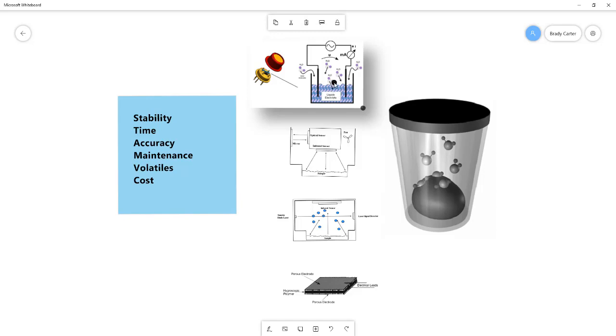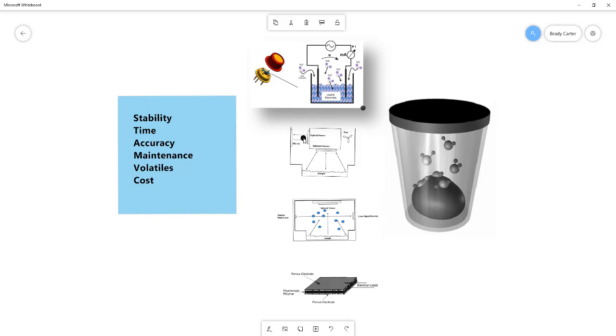The electrolytic sensor measures it by tracking changes in the resistivity of an electrolyte solution as humidity changes. Similarly, the capacitance sensor measures the changes in electrical properties of a hygroscopic polymer due to exposure to different humidity conditions, while the dew point sensor measures the vapor pressure inside of the chamber by the dew point temperature, and then the saturated vapor pressure based on the sample temperature and the two together give the relative humidity or water activity. And a tunable diode laser has a laser tuned to a wavelength that's specific to water, which can then measure vapor density inside the chamber, which then relates to vapor pressure, and also measures the sample temperature to get the saturated vapor pressure.